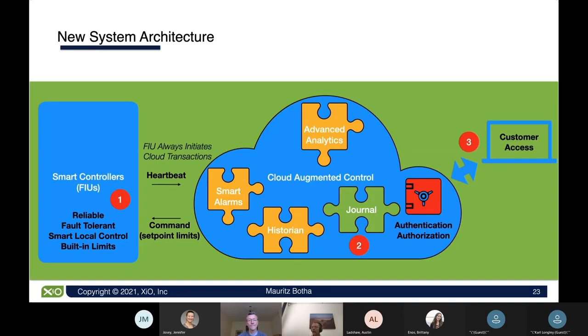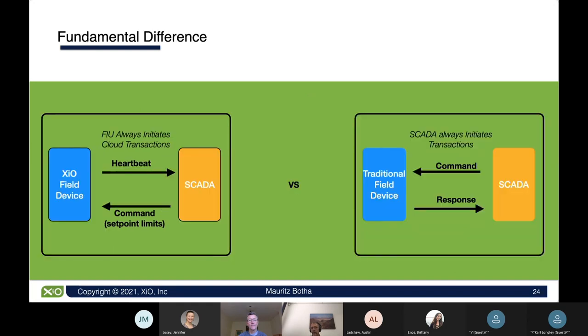Finally, the customer access is secure, just as secure as any modern internet-based system would be. Here's the fundamental difference: on the right-hand side in traditional systems, the SCADA system always sends a command, and the traditional field device responds to it without really knowing where the command originated. With our system, the field installable unit always initiates the transaction, sending a heartbeat to the cloud, and the cloud can then respond with a command.